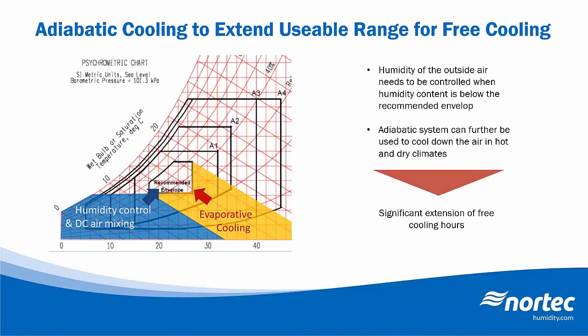Now, if we were to couple an airside economizer with an evaporative cooling technology, we could further increase the airside economization hours simply by allowing warmer outside air temperature and cooling it down through the evaporative cooler. So if you look at this on a psychrometric chart, any outside air condition in the blue section would be a mixture of humidity control and economizer operation to get us into that recommended range. And any condition in the yellow section there could be achieved just using straight evaporative cooling.